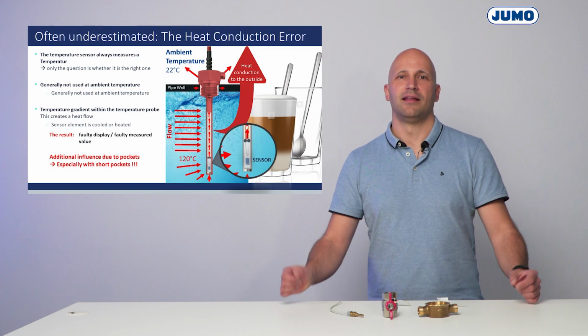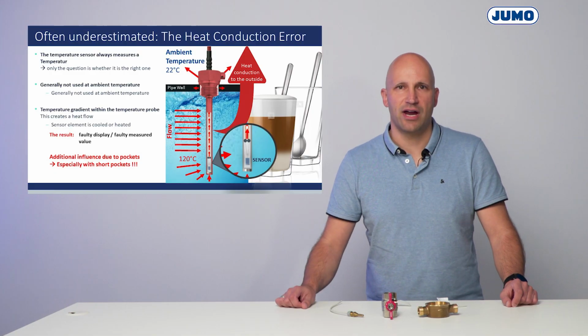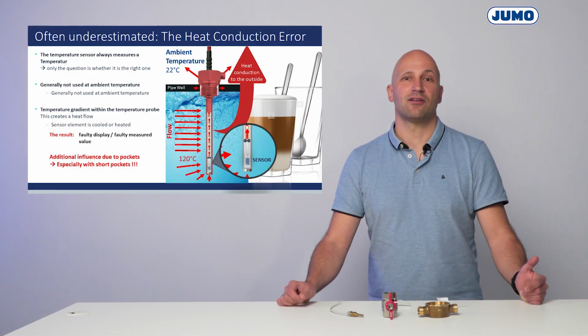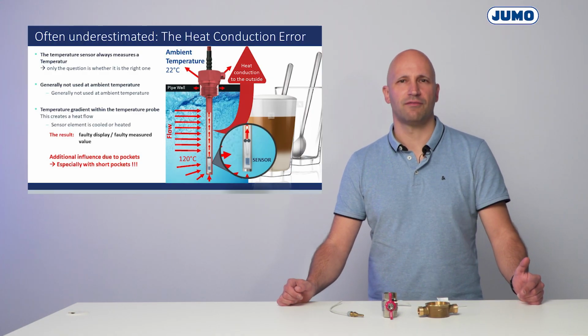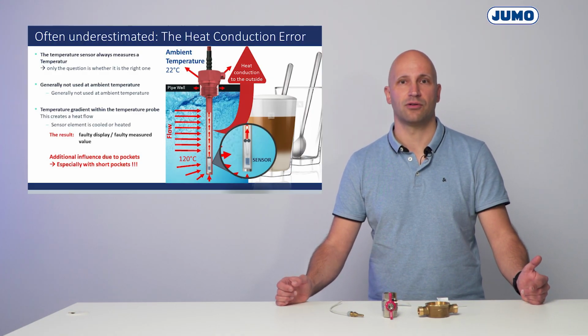In this video I would like to show you how important the correct installation of temperature probes is when installing heat and cold meters. In particular, I will highlight the differences between symmetrical and asymmetrical installation and effects such as the heat conduction error. This may sound a bit technical, but I promise it's worth taking a closer look, especially if you want to ensure accurate temperature measurement. Let's talk about precisely this heat conduction error in a moment. An issue that is often underestimated, but it's crucial for measuring accuracy and therefore for billing heating costs.